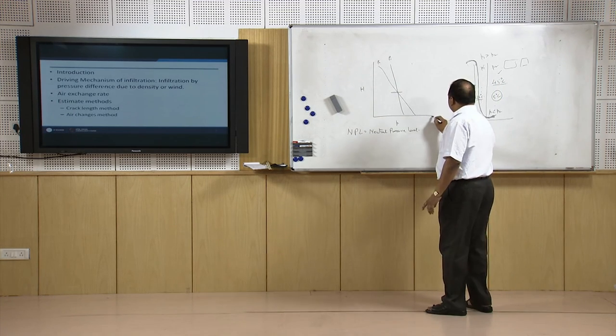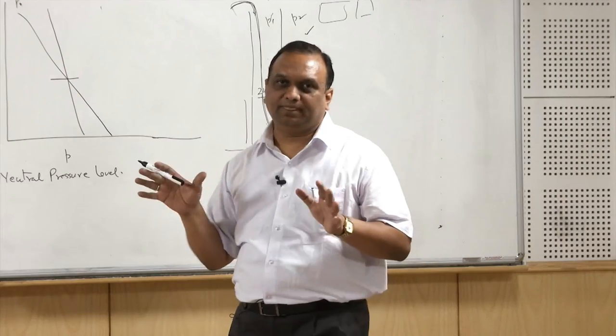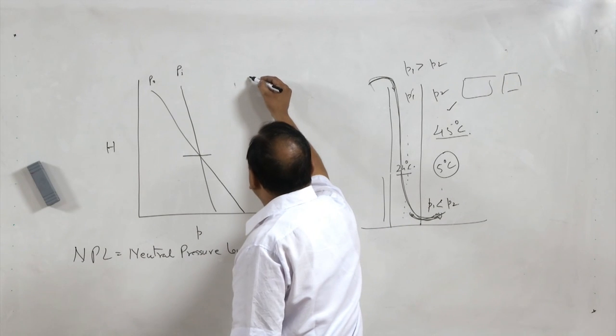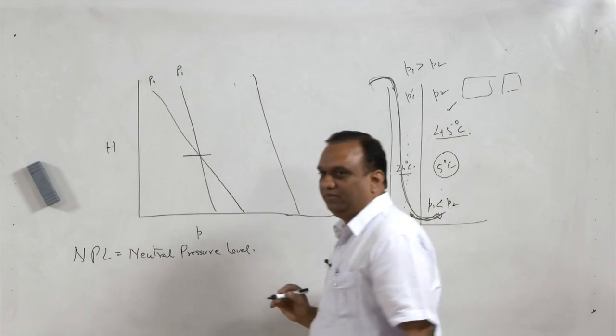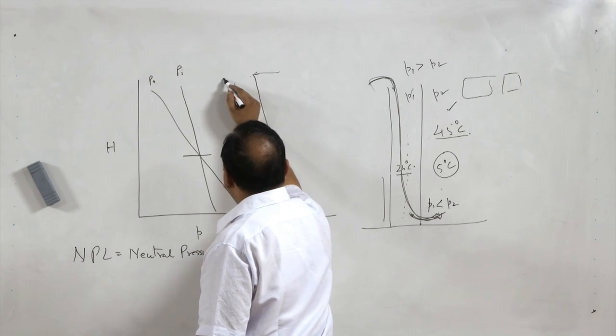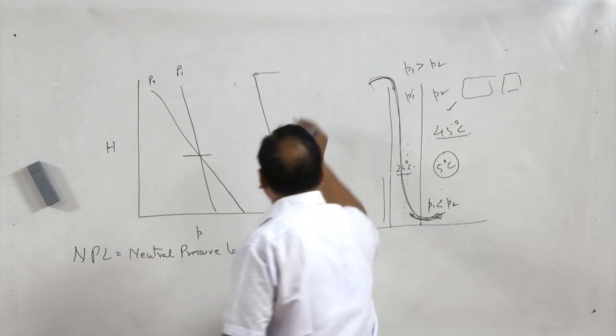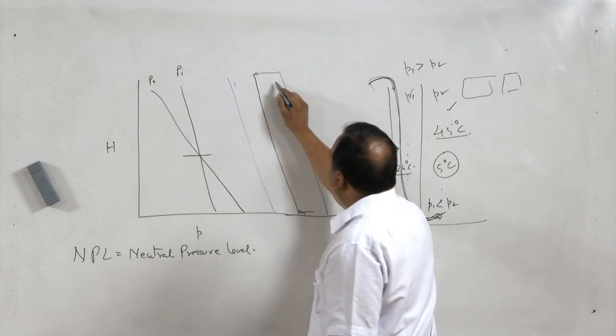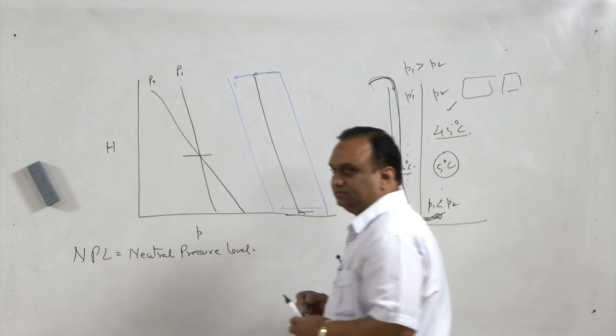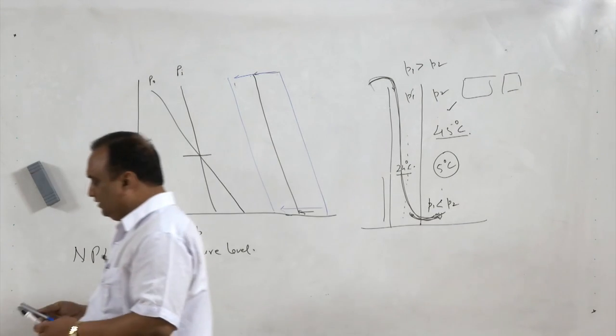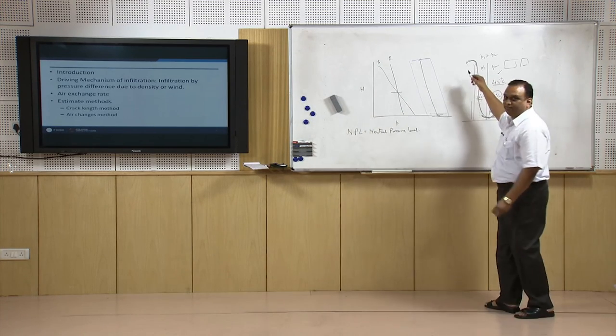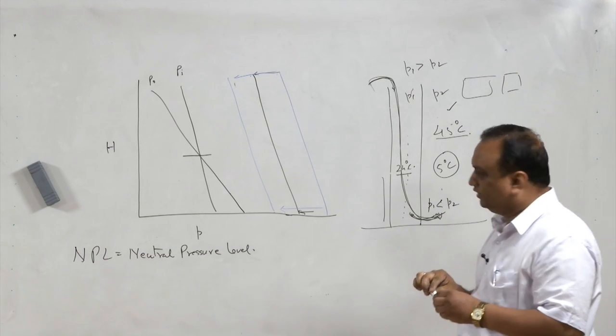Now regarding wind-driven infiltration: air is also moving with certain velocity. When wind moves across a building, the building acts as a bluff body. On the windward side there is positive pressure, and on the leeward side there is negative pressure. This causes air to flow into the building on one side and out the other. If wind velocity is high, air can enter from all possible points in the building.